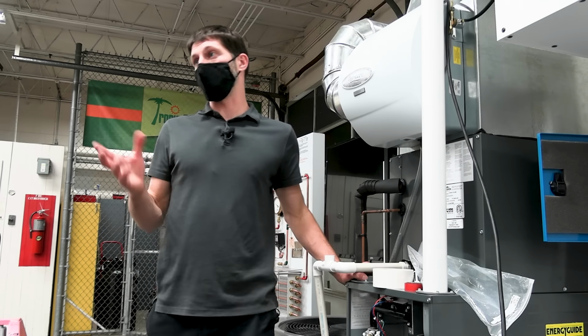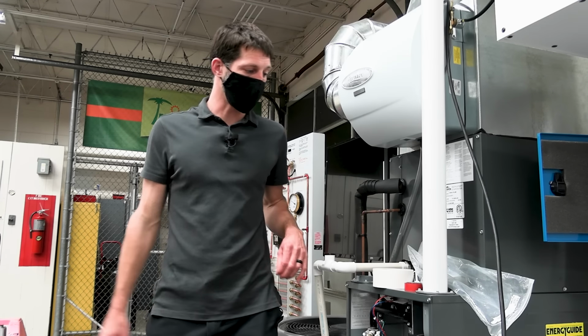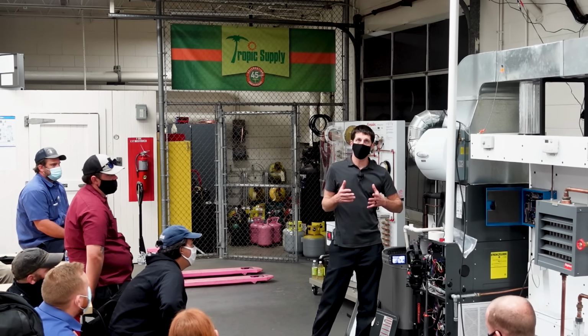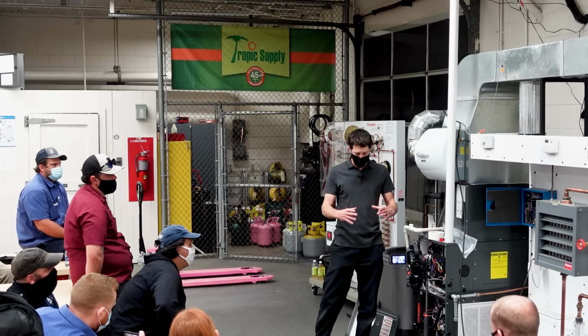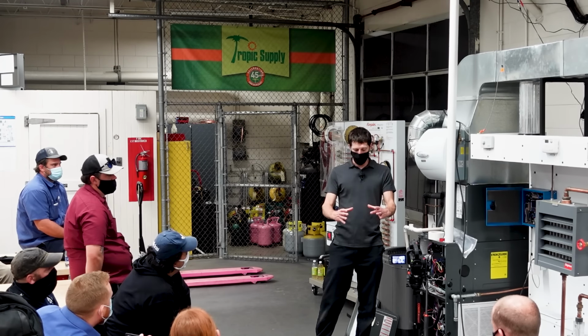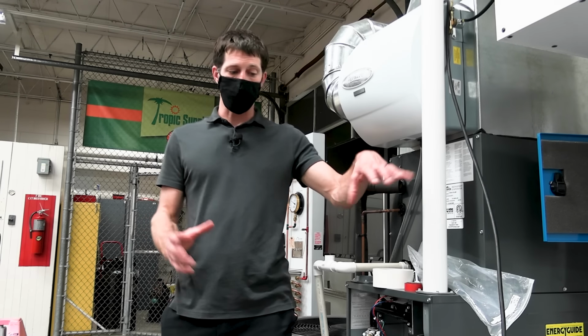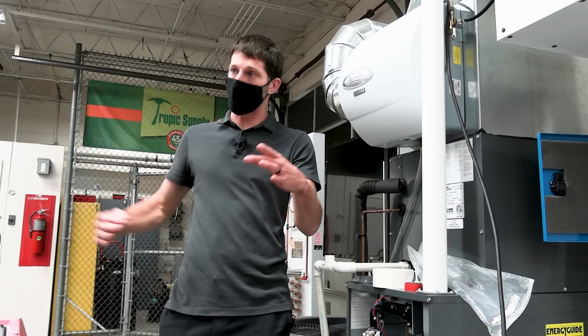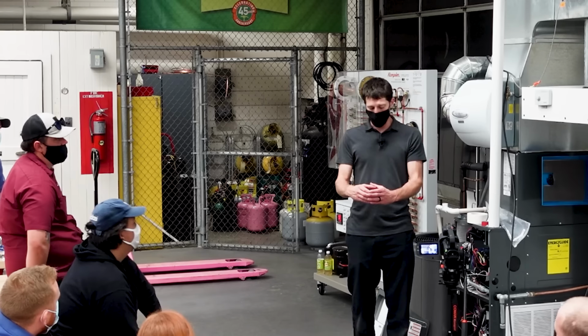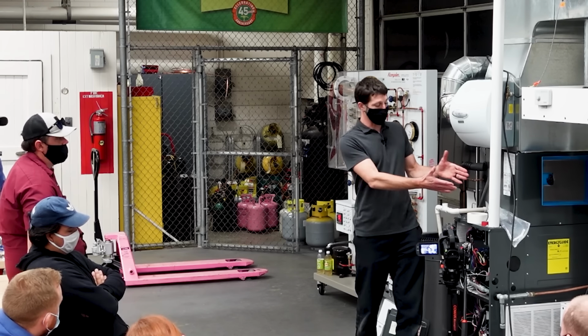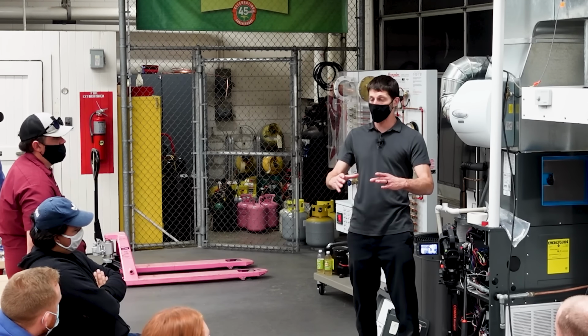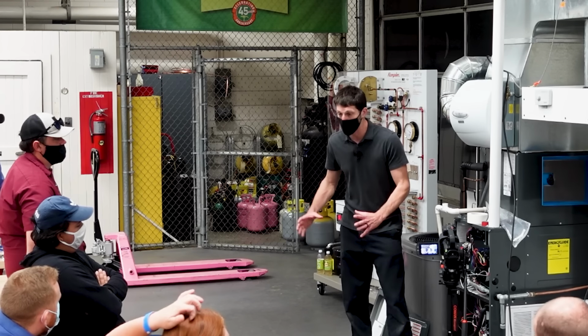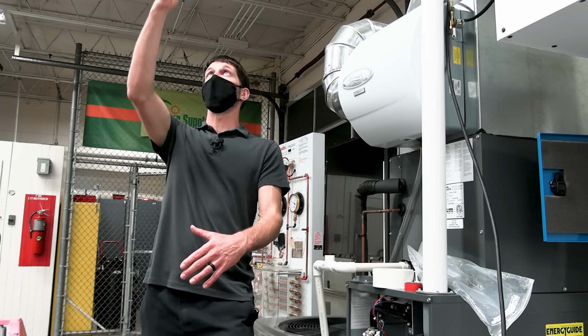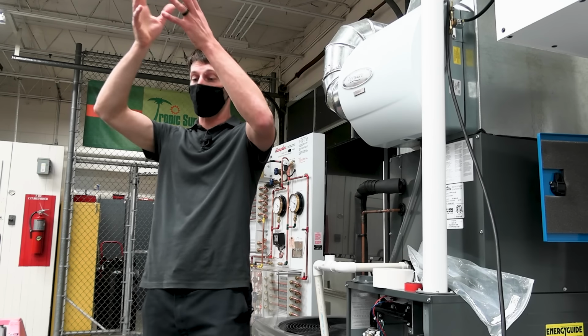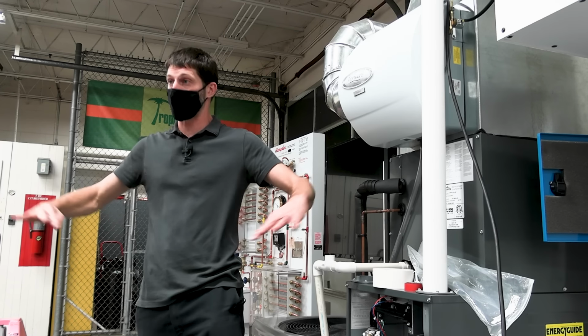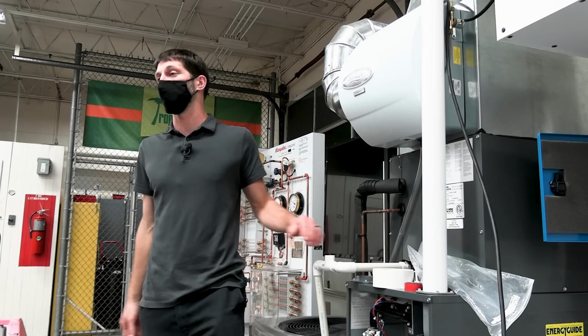That's huge. You know, that's the big thing when you have a water heater there. Yeah. There's also what's called orphaning. What is it? Orphaning the water heater. It's basically you have a large exhaust pipe. And so basically you had maybe a boiler or an old gas furnace going up into a shared exhaust with a water heater, and the water heater has a small exhaust pipe. And so what happens is then you upgrade to a higher efficiency gas furnace, and you're left with this large exhaust pipe. And what happens is there's not enough heat from the water heater for the combustion air to rise. Eventually what happens is it's just not hot enough, and then it comes back down through the natural draft air intake back into the room, and now you have carbon monoxide in the building.